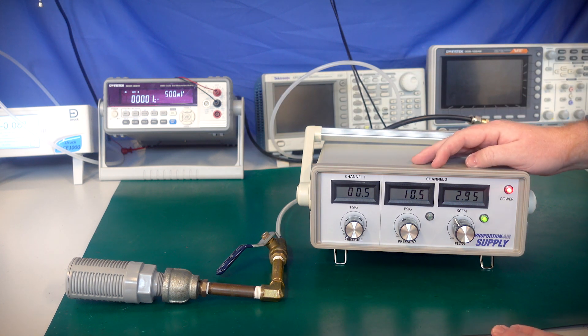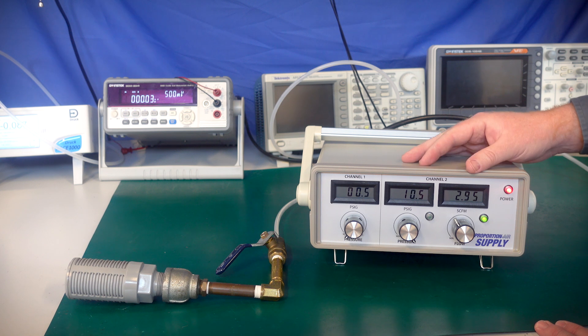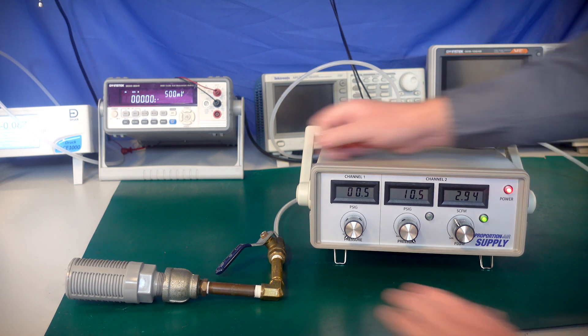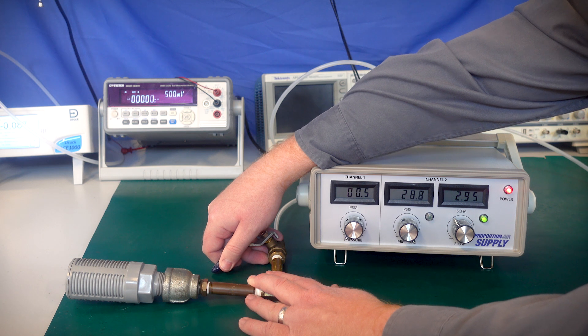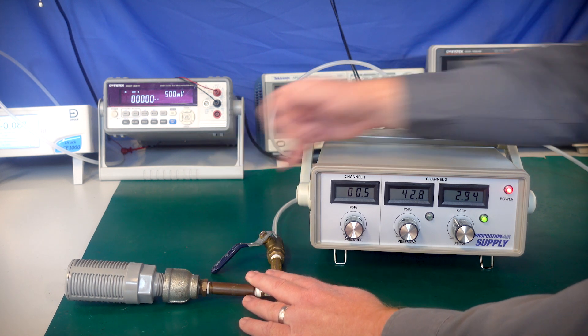So you can see here with the ball valve closed about 50%, in order to keep the almost 3 SCFM, you now had to jump up to 10 psi. If you close more, it will keep going up to 40 psi, up until the max of your tubing going into the unit.